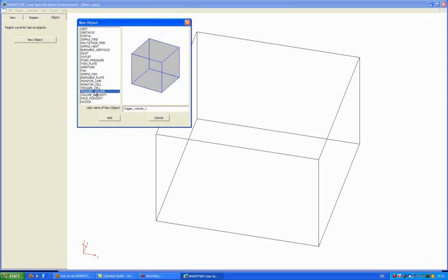The trigger volume is similar, except that it allows a collection of cells to be averaged or maximum values to be taken within that region. A volume porosity allows partial volume flows to be defined. Face porosity defines partial blockages of areas, and a nozzle provides source of droplets for sprinklers or mist systems.